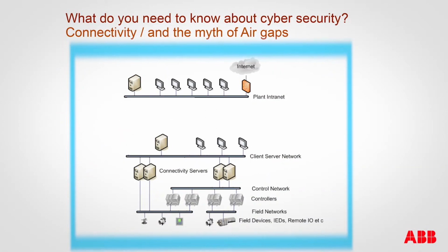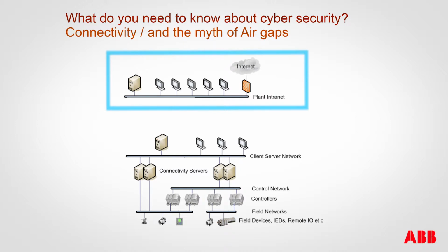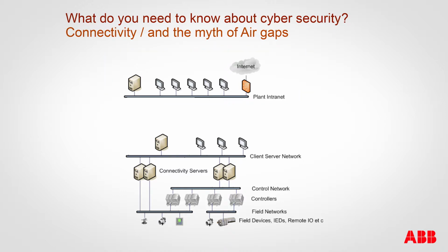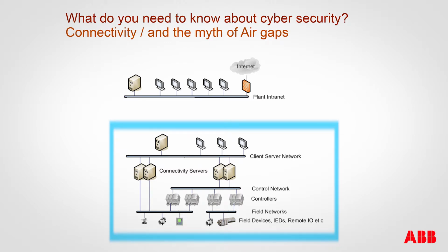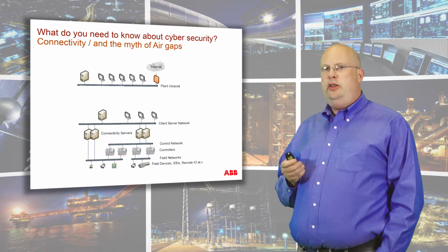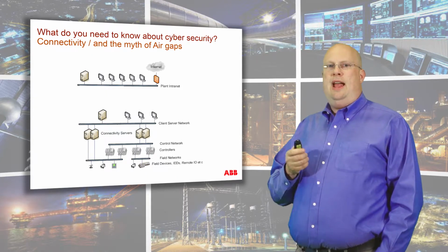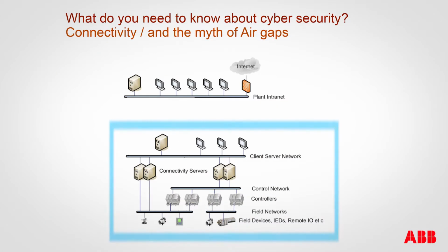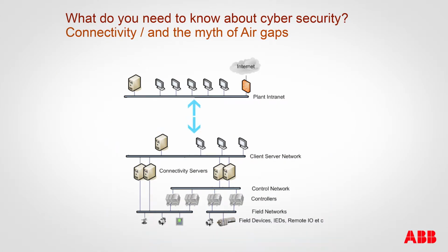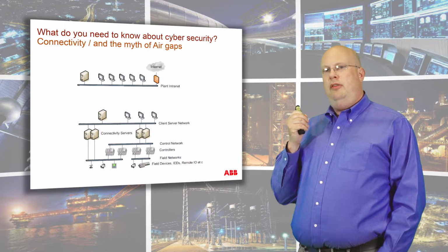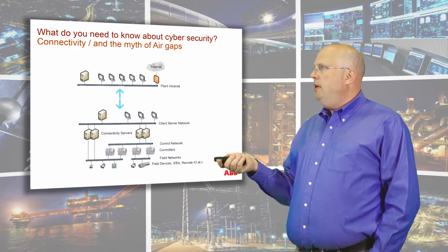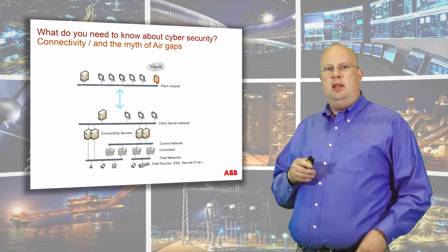First of all, even if you would have this, which I doubt strongly, sooner or later a manager up here is going to say, I want data from the production. I want to know how much we're producing or how much material we're using or what the stock levels are. So someone will go down to the control system where all the data is electronically stored today. And he will probably not use a pen and paper to write up the trend for the last year. Most likely, some kind of electronic media will be used to transfer that information. Most likely a USB stick. There you have a connection. That USB stick could be infected and the air gap is being bridged, and therefore that whole argument has fallen flat.